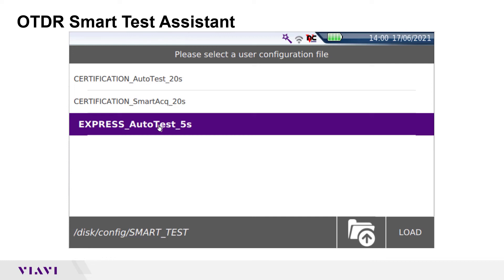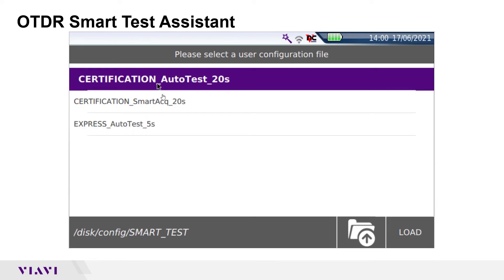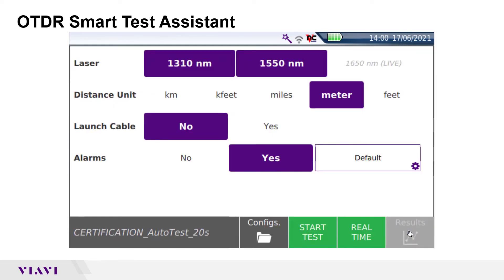I will select Auto Test and tap the Load button to load it. There are only four settings to configure when you use Smart Test Assistant. Laser lets you select which lasers to operate. I'm going to select 1310 and 1550 to enable bend detection.